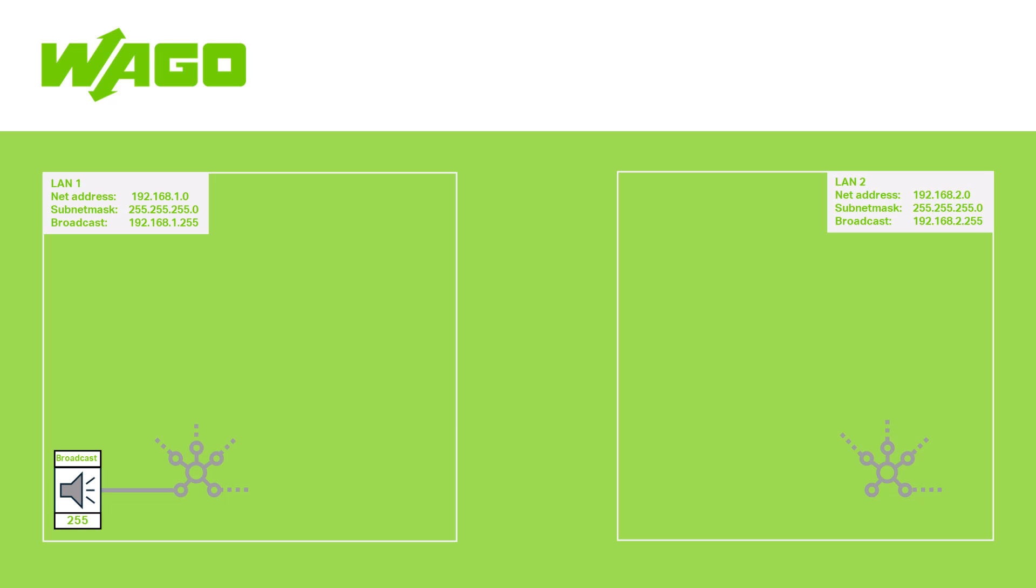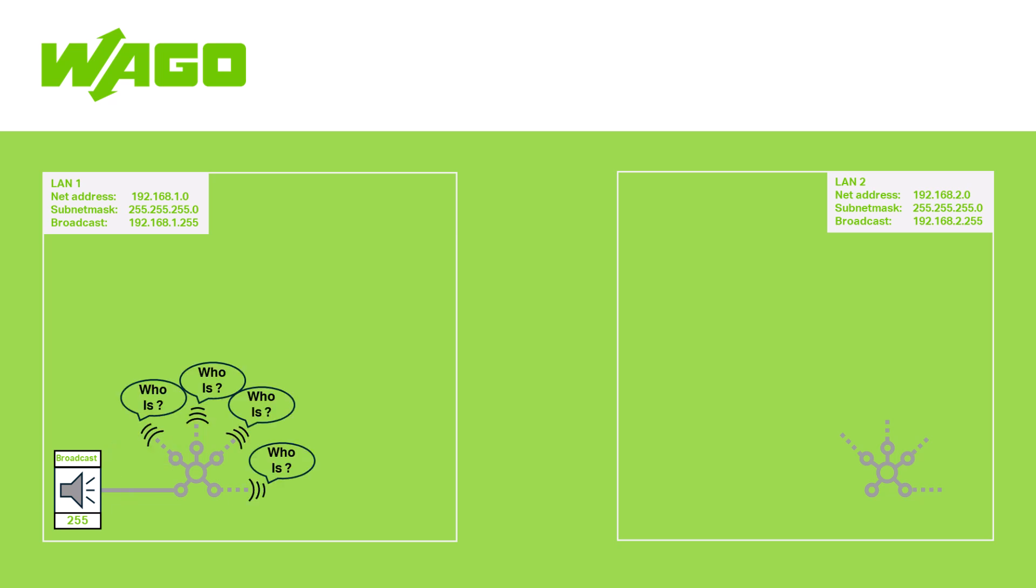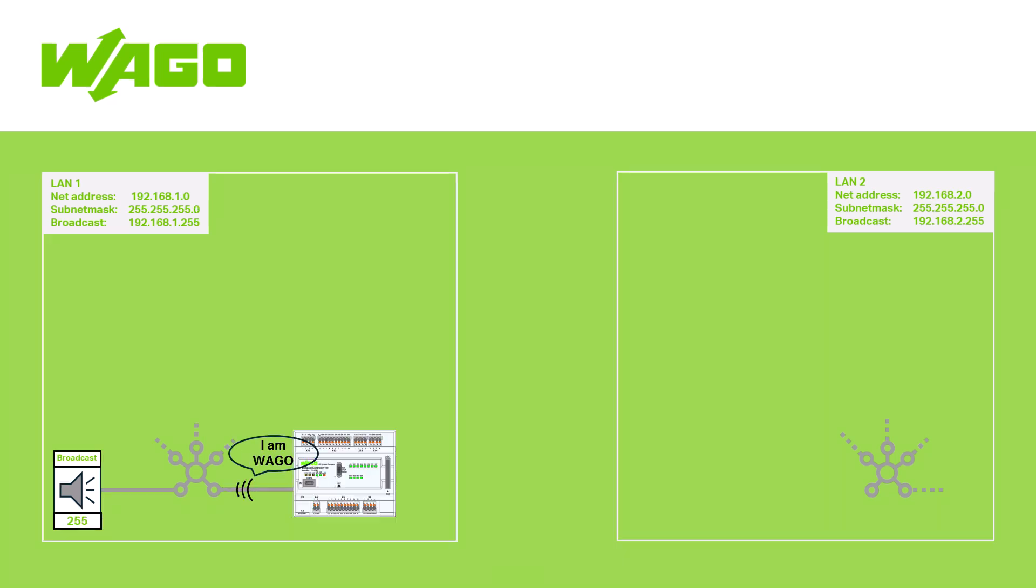If we send a telegram to 192.168.1.255, it will be received by all devices on the subnet. BACnet uses this broadcast feature in several services. One example is the WHOIS service to identify all active BACnet devices. When a BACnet device sends a WHOIS message, it is received by all BACnet devices, which respond with IAM, their MAC address, and BACnet ID.